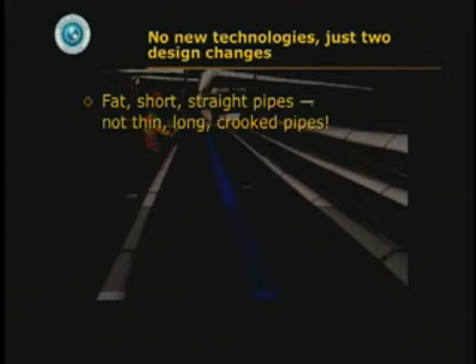Now, the pipe fitters think this is wonderful—you pay them by the hour, they mark up the extra pipes and fittings, but they're not going to pay for your bigger pumping equipment, nor your bigger electric bill forever after. For you as owner, it would of course be more intelligent to have fat, short, straight pipes rather than skinny, long, crooked pipes. This gives us a factor of 12 or so reduction in the pumping energy.